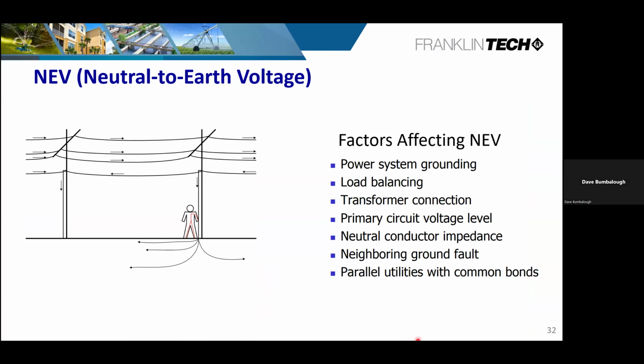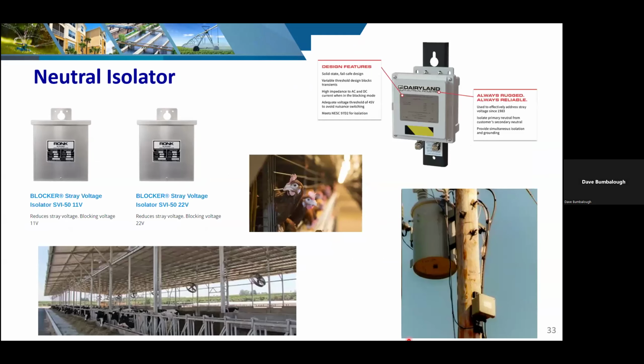We also have to worry about situations where, potential shock hazards, the safety ground, what the power company refers to as NEV, neutral to earth voltages. Okay, so that's stray voltages kind of back there on that same picture that I showed with the animal confinement. Something's happening where that voltage is being leaked. Okay, now the power company does have the ability, even yourself, if you wanted to front the cost, but they've called it a neutral isolator. If you can't get the safety ground cleared up, the power company, as you can see in this picture, can install what's called a neutral isolator, and I assure you, those do work. I've seen them in practice. They do work. They will eliminate any kind of stray voltages coming in.